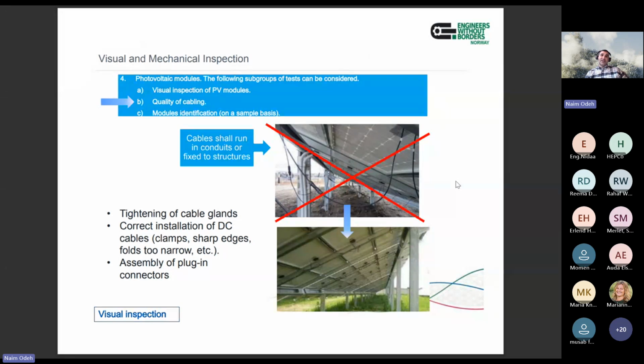We explained this point, and I can repeat it quickly. MC4 connectors should not be in this position, should not be in the lower position. They have built-in protection - there is rubber inside where water doesn't easily get in - but by time, as we design these projects for 20 or 25 years as a lifetime, it is expected that over time, with a water drop within the wire touching the MC4 connectors, it will happen. That doesn't mean it will happen in the first or second year, but it may happen after 10 or 15 years, and when it happens, the impact is very huge.